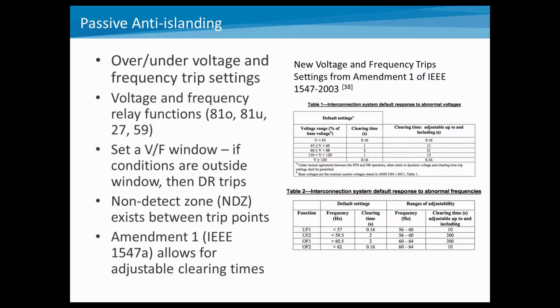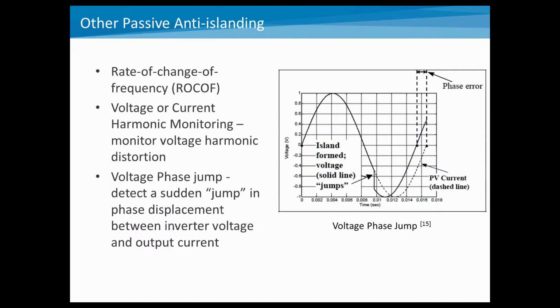The big thing here is that the new amendment to 1547 allows for adjustable clearing times. And you can see some of these clearing times are opening up much wider. For example, in the table, if you looked at the voltage between 45 and 60%, the clearing time used to be 1 second. Now you can adjust that all the way to 11 seconds. And this is accommodating things like low voltage ride-through capability, but that's also going to open up your passive anti-islanding windows.